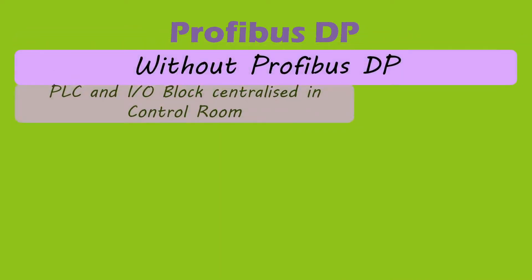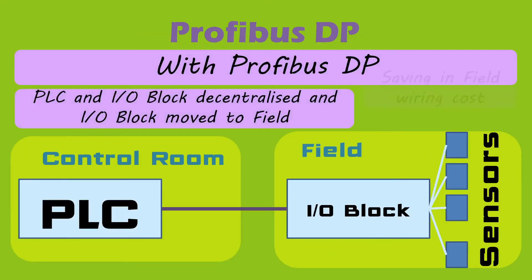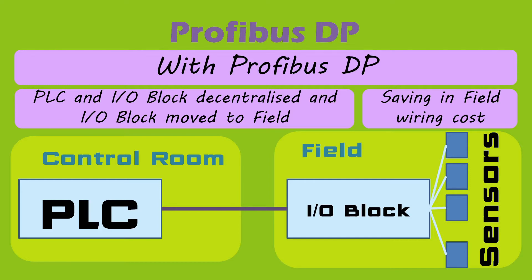Profibus DP stands for Decentralized Peripherals or Distributed Peripheral. Initially, all IO blocks or peripherals were installed in control room panels and sensors were connected through wires from the IO block to the field — meaning everything was centralized. With Profibus DP, the IO block could be carried to the field and sensors connected to the IO in the field itself, with information transmitted through Profibus to the central controller in the control room. Thus, the IO block was decentralized, and the variant was named Profibus DP.